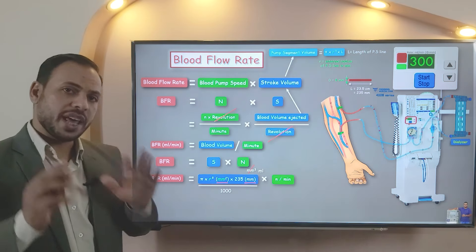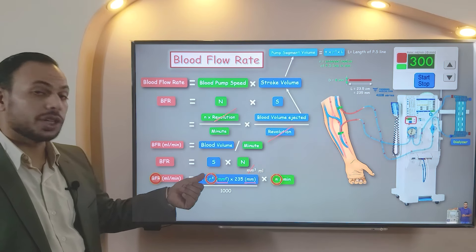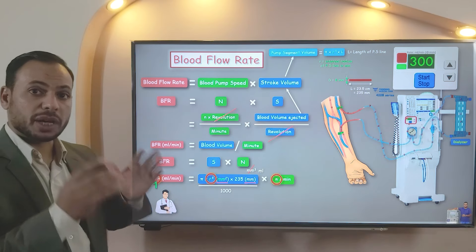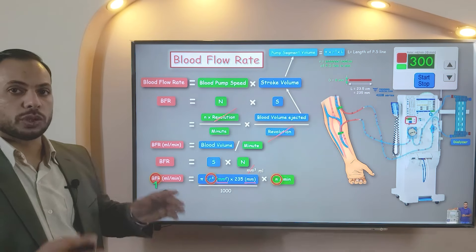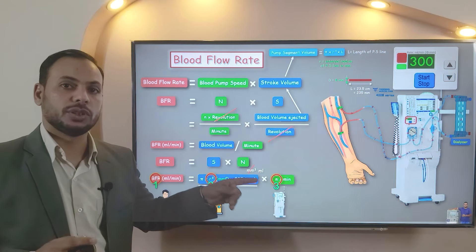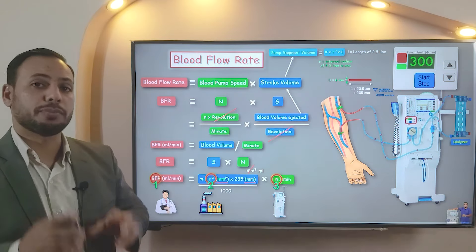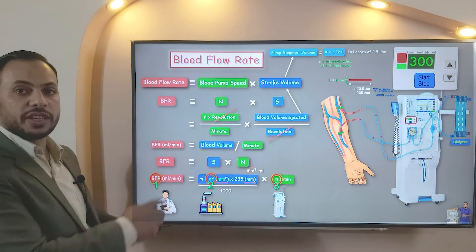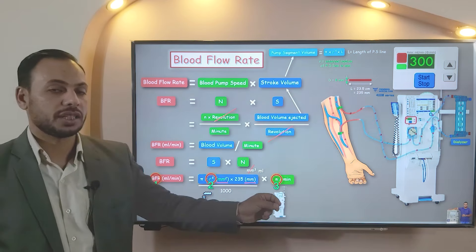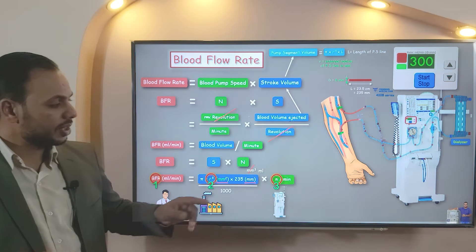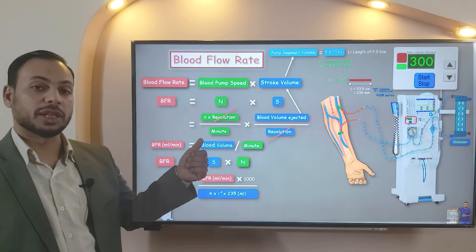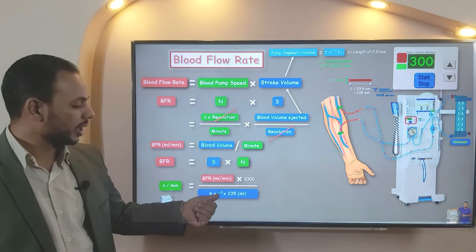We now have three variables: the blood flow rate, the internal radius of the pump segment, and the number of revolutions per minute. The blood flow rate is assigned by the physician according to the patient's parameters. The internal radius is assigned by the manufacturer of the blood lines or tubing set. The third variable — number of revolutions per minute — is calculated by the machine based on the entries of the other two variables. Rearranging the equation from the machine's point of view: N = (BFR × 1000) / (π·R² × 235). This is a very important equation.